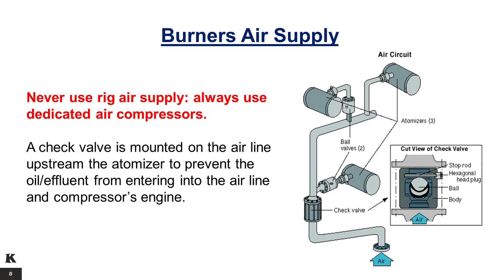Burners Air Supply. Never use rig air supply to supply the burner. Always use dedicated air compressors with enough air capacity. Generally, two compressors are used as backups for continuous burning operation. A check valve is mounted on the air line, upstream of the atomizer, to prevent the oil or effluent from entering into the air line and compressor's engine.